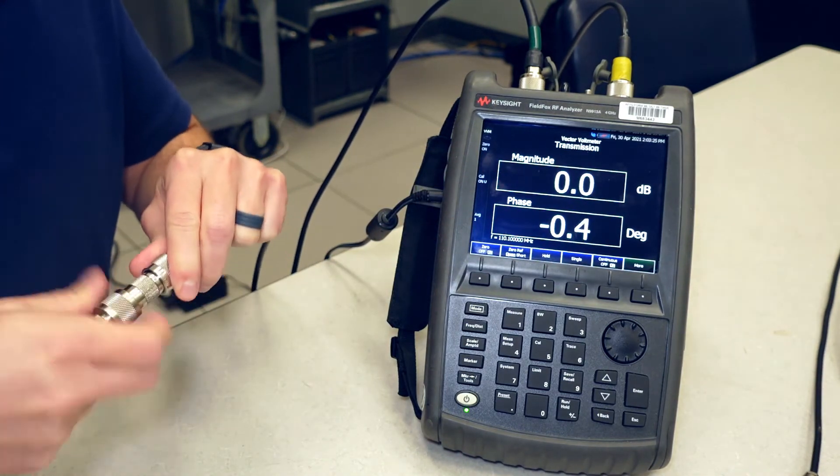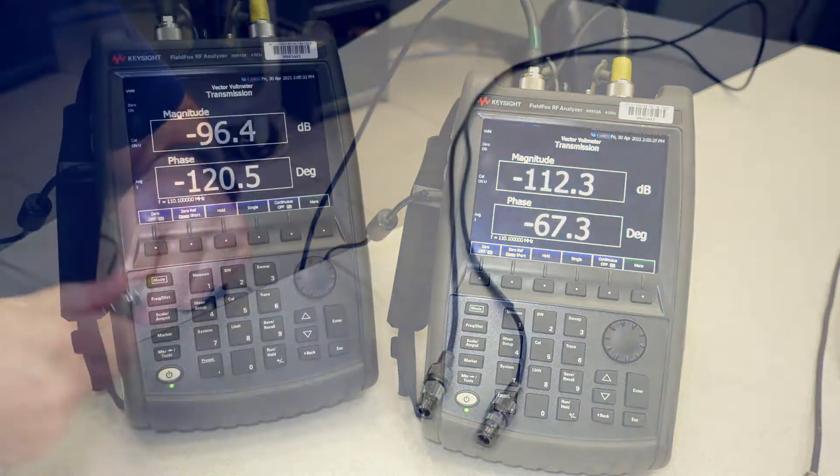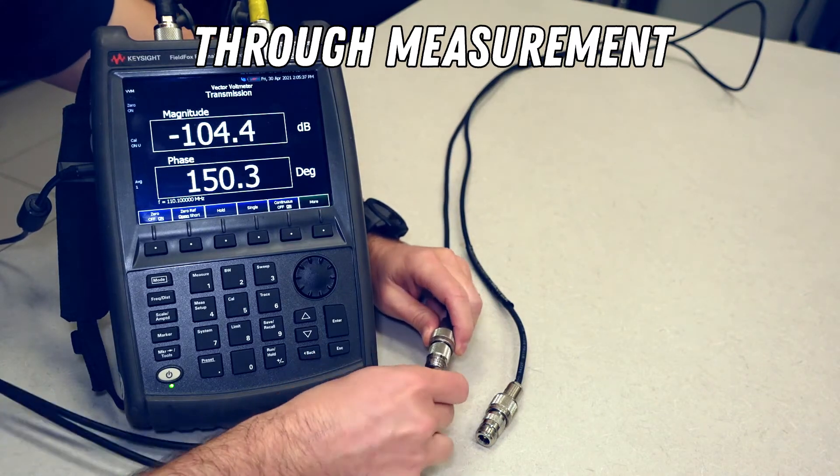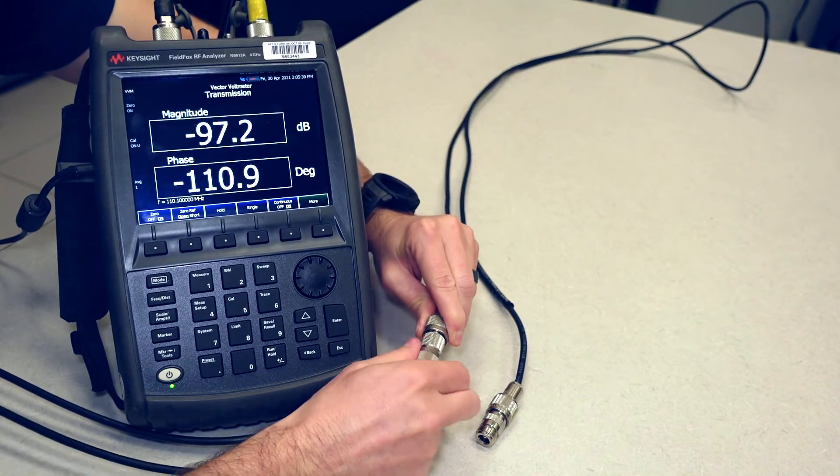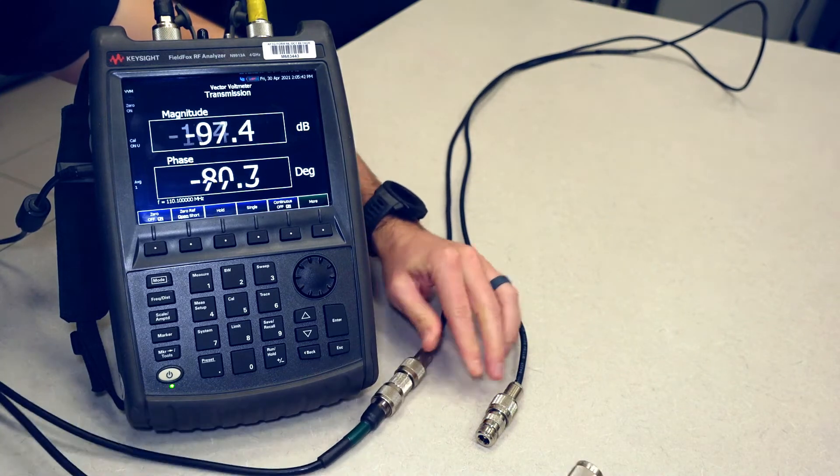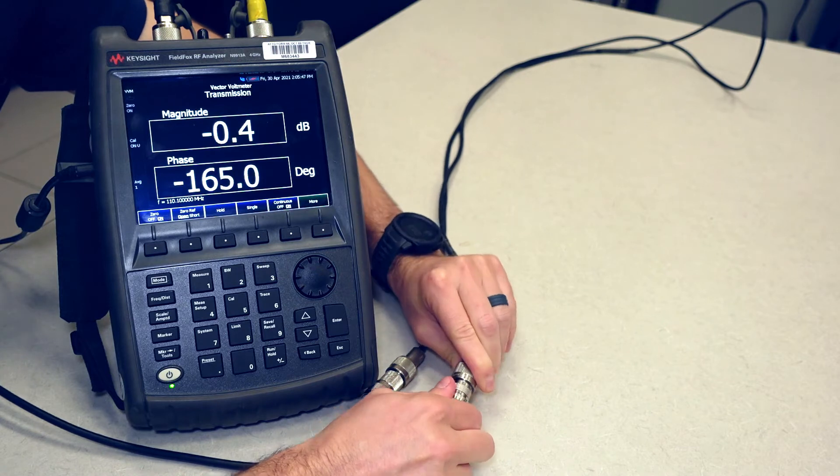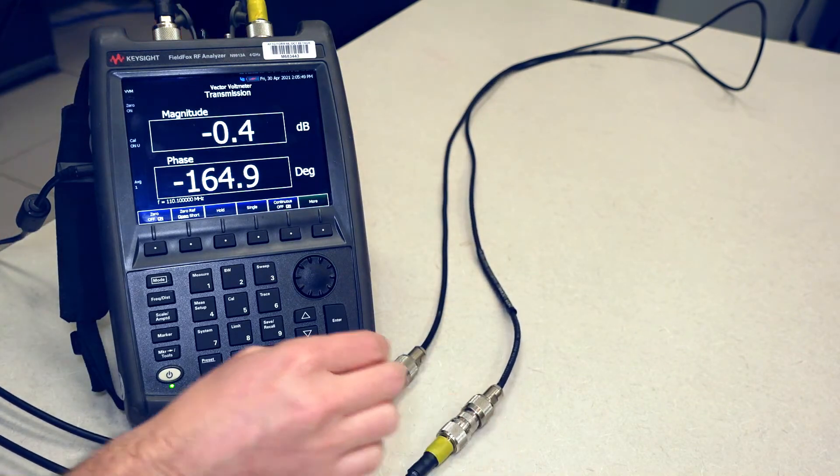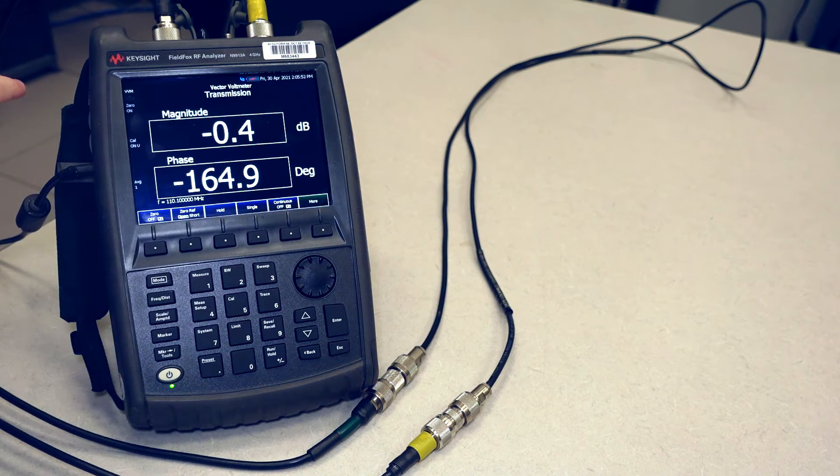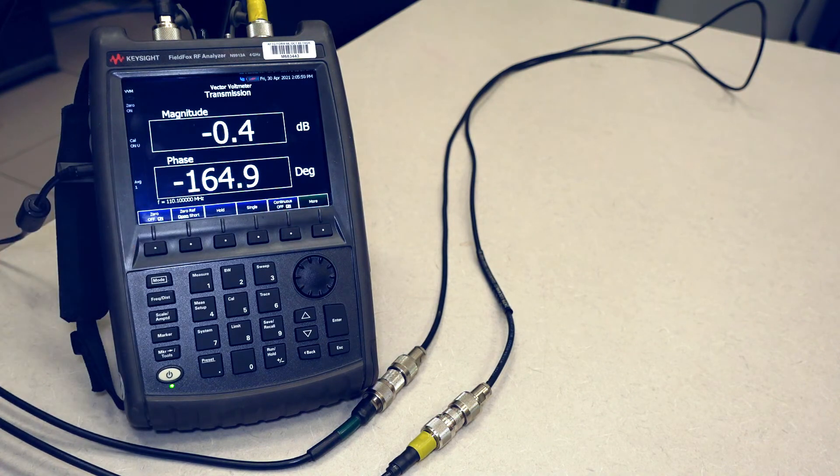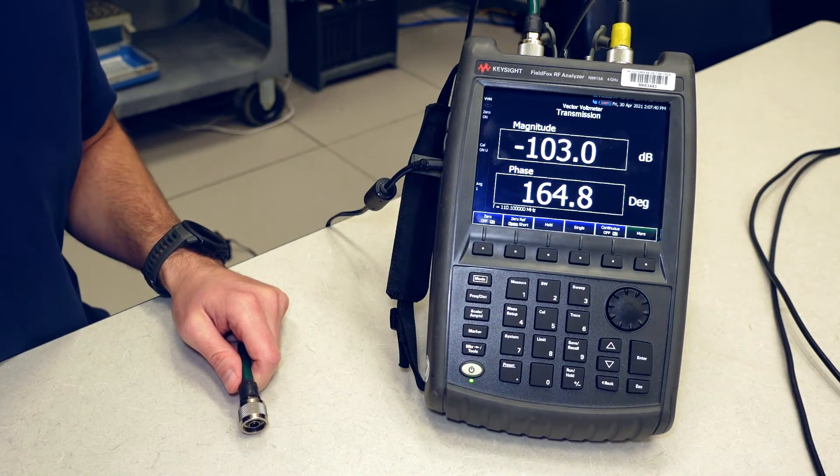Now we can connect to whatever device under test that we want to look through. So for this example of a through type measurement, I've got a test cable here on the table that we're going to connect port one to one side and port two to the other. And the FieldFox is telling us that this little bit of test cable, it's about eight feet long, has a loss of 0.4 dB and we call that an insertion loss. And the correction of the phase is a negative 164.9 degrees.